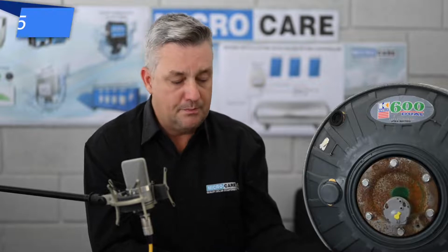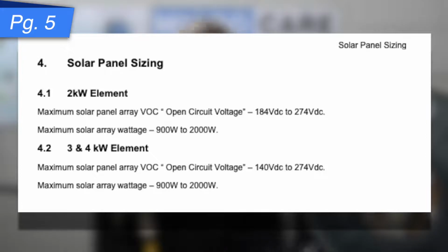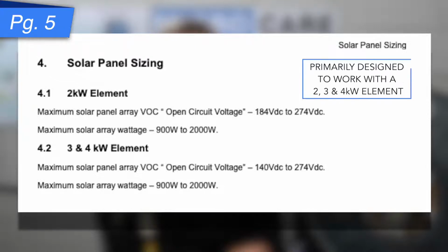We move over to page number 5 and number 4, very important now, solar panel sizing, and you'll note that our 2 kilowatt element has a different power requirement to any 3 and 4 kilowatt element. I often get asked, can I do a 5 kilowatt element? Can I do a 1 kilowatt? Please make sure you touch base with our factory before you go ahead with those systems. This is primarily designed to work with a 2, 3 and 4 kilowatt element.